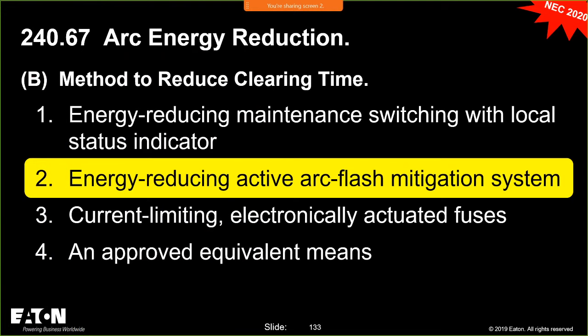That's typically how you're going to see these tests done in the field. Some sort of testing unit that's separate, and the breaker is going to be racked out. If it's a fusible switch, the relays and CTs will be inside, and you'll have a piece of equipment that'll inject current. Now, my advice is you don't have to inject the full current. You can just inject enough current to make sure that the device is operating and functioning. You're not going to be putting 40-some thousand amps through that piece of equipment or that breaker. You're putting something much less, just to make sure that it is functioning.